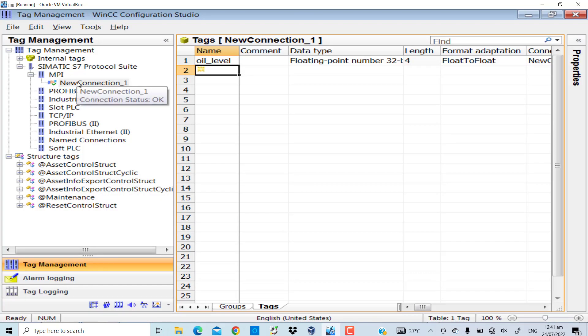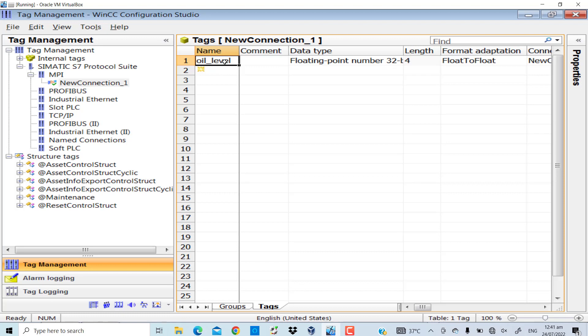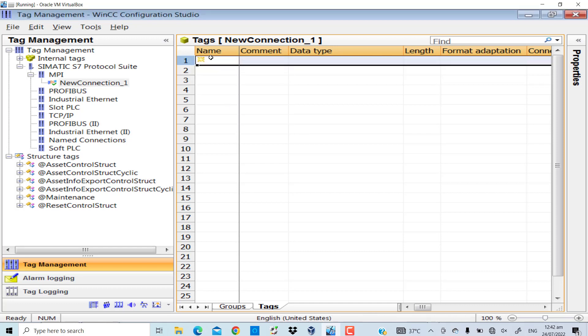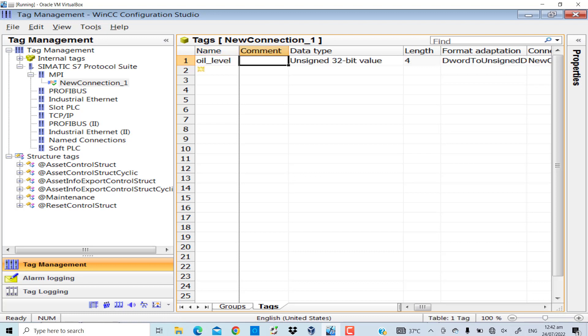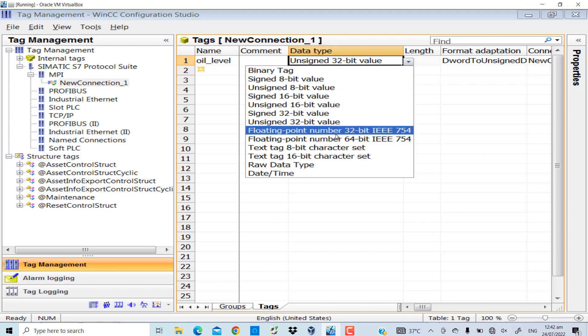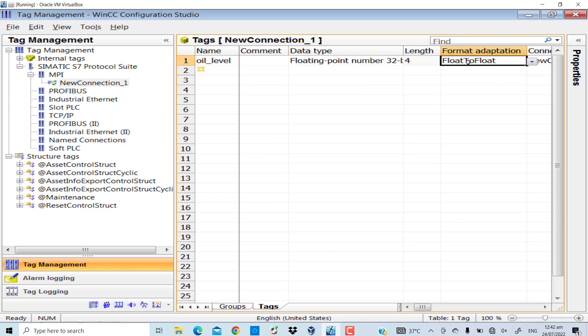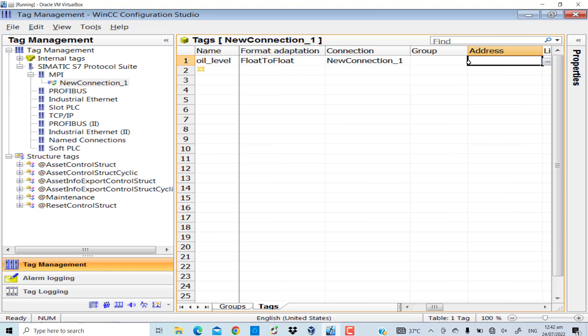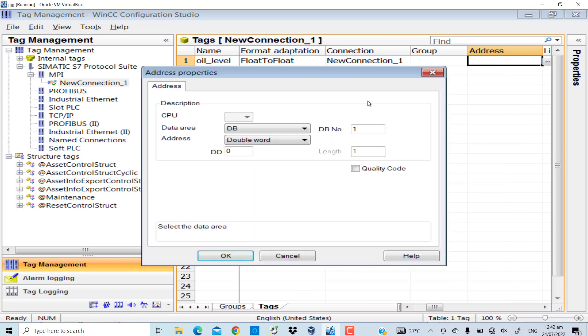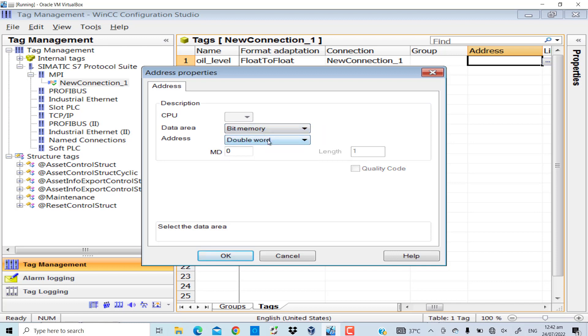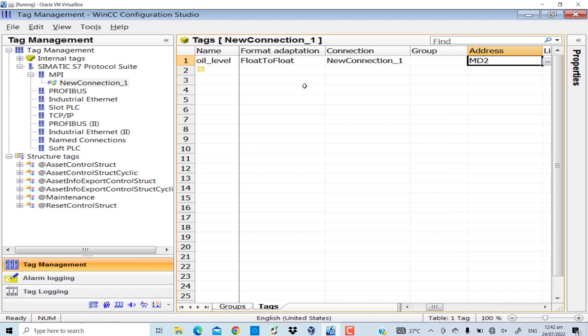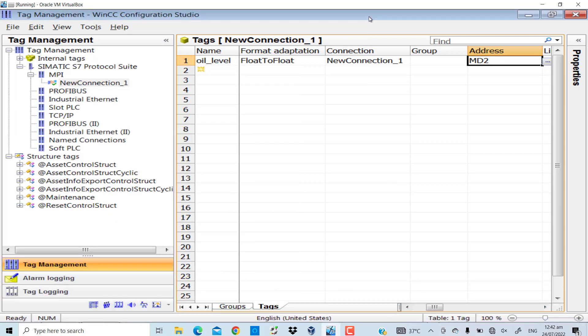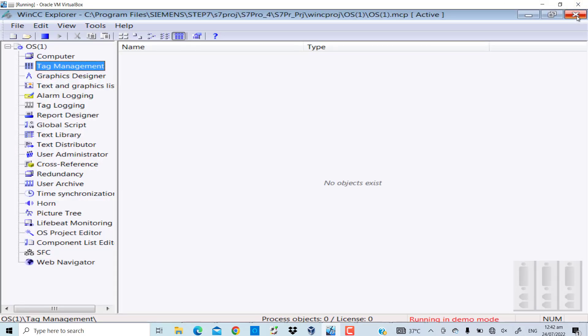Go to the tag management section. I've already added my desired tag, the oil level, but let me delete it and add it all the way from the beginning. The data type is floating point 32 bit, address is MD2 - bit memory double word 2. Okay, the MD2 variable has been successfully added to the tags of WinCC.